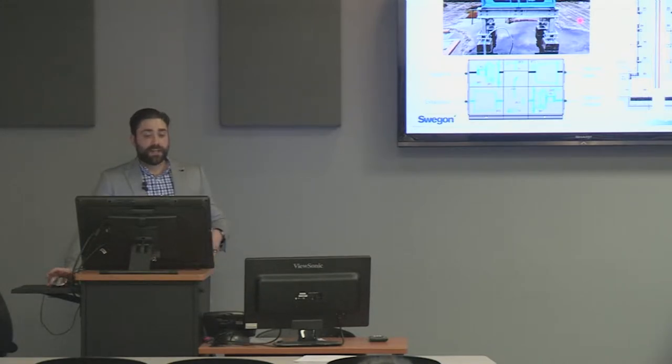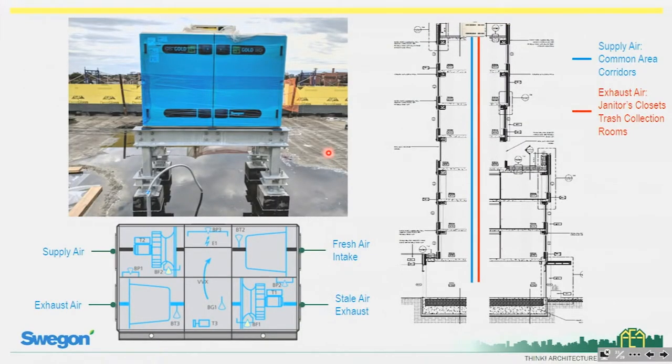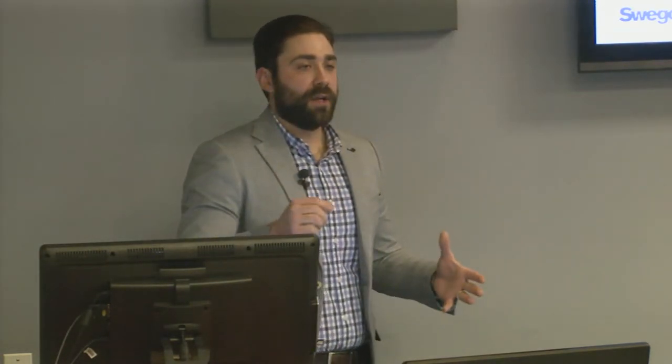What's nice about the Swegon unit compared to the Zehnder unit? The Zehnder unit is a fixed core — whatever goes through that unit goes through a fixed counterflow heat exchanger. Whereas the Swegon RX Gold is actually a rotary heat exchanger. Not only can I slow down or increase the rate of airflow through the ventilation system itself, I can also slow down the rate of heat exchange by controlling the speed of the wheel. As I increase or decrease the speed of the wheel, I can proportionally increase or decrease the amount of heat energy going through, as well as vary the fan speed. So by having control over both the heat exchange and the airflow, I can achieve a really high level of precision in terms of the amount of heat I recover and the comfort maintained inside the building.